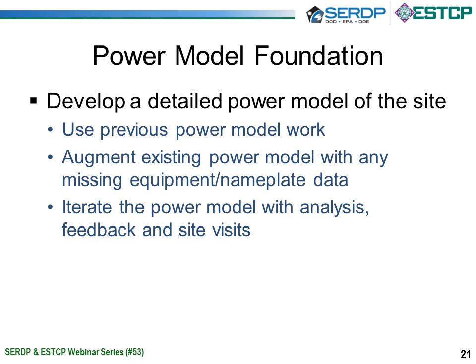The power model, as I mentioned, is pretty fundamental to how we approach a system like this. The basic idea of the power model is that it's designed to tell you significant information about the electrical infrastructure. Historically, most people are familiar with the benefits of a power model through specific deliverables often referred to as protective device coordination, short circuit analysis, or more commonly these days, arc flash analysis. That's largely because delivering the right level of power to specific locations is the fundamental need for a power network in the first place.